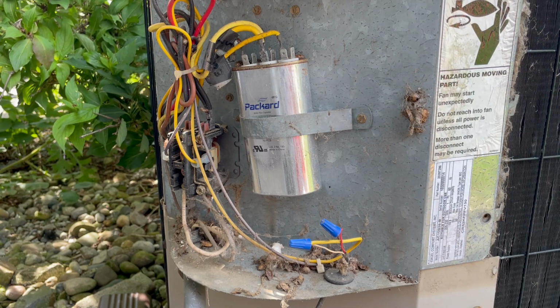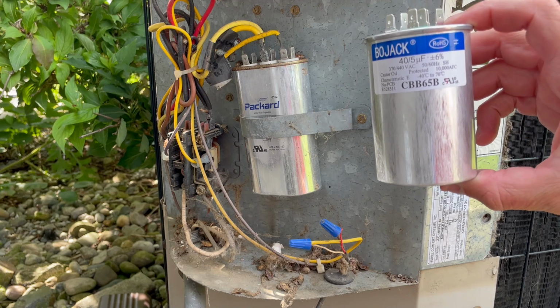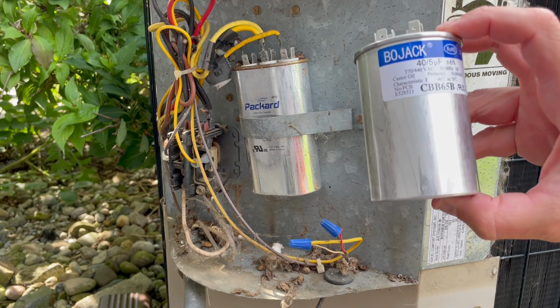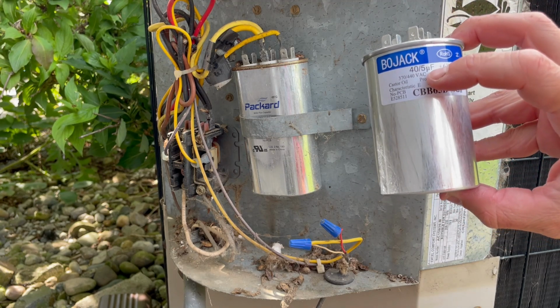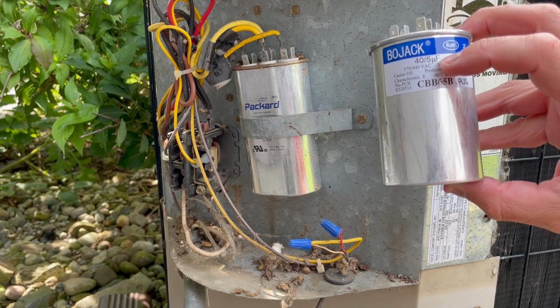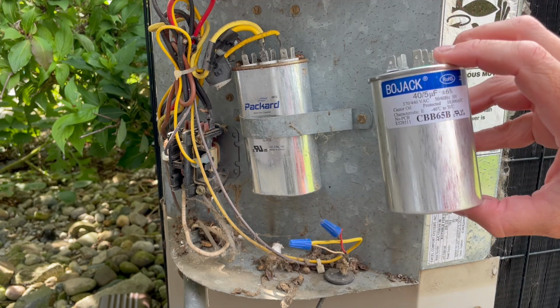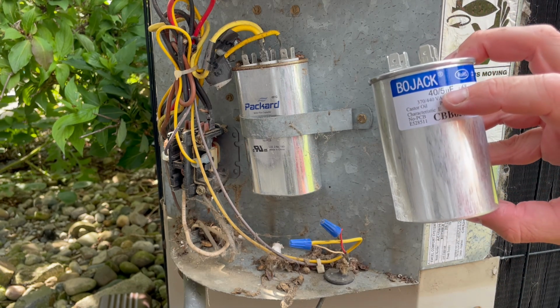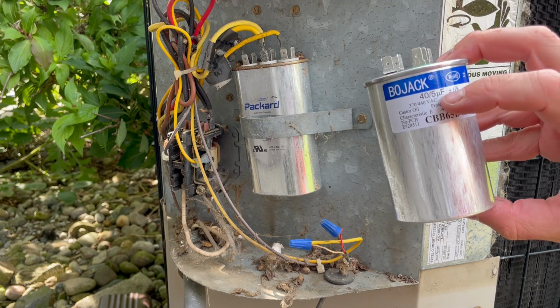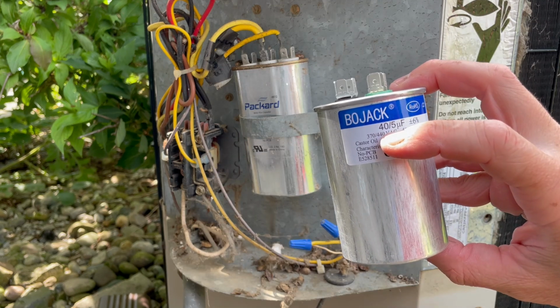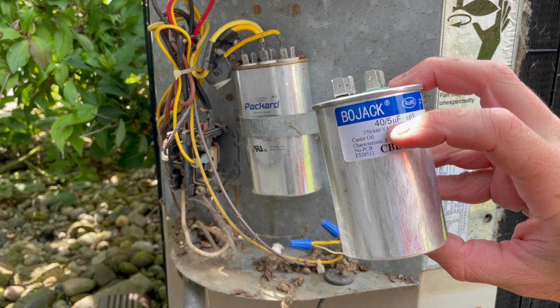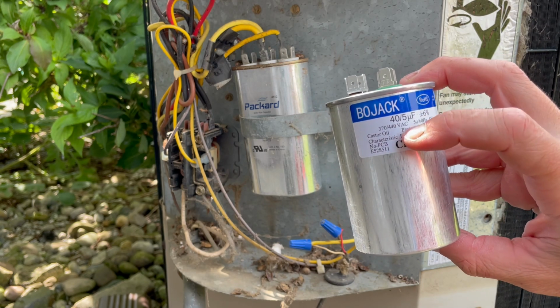So we've gone ahead and ordered a replacement on Amazon. The important thing is to make sure the specs on your replacement match what's currently installed. In this case, we've got 40/5 microfarads. So 40 microfarads to run the compressor and 5 to run the fan. That's what those two numbers mean.